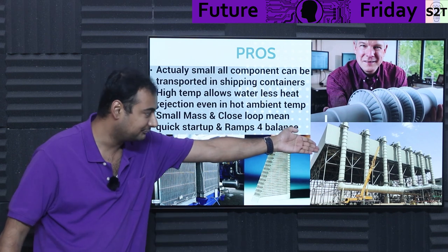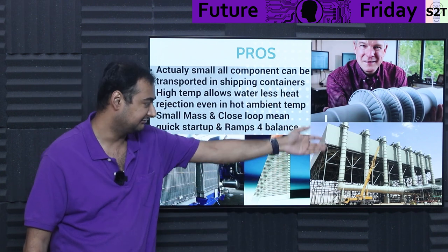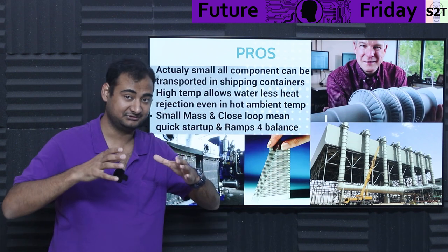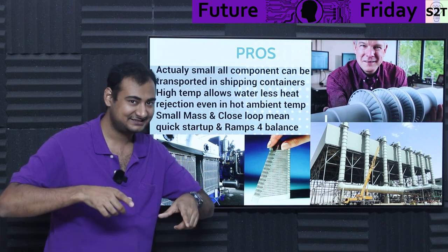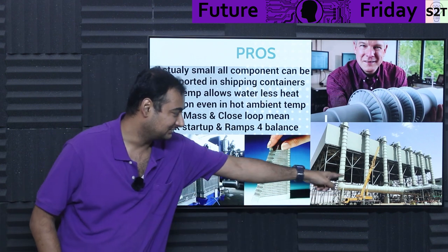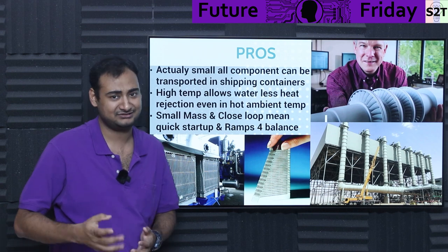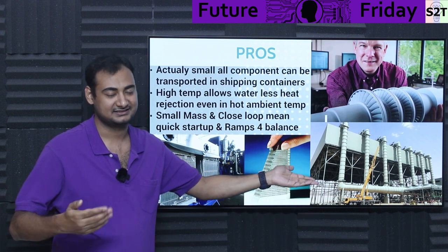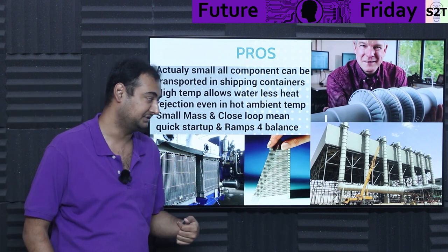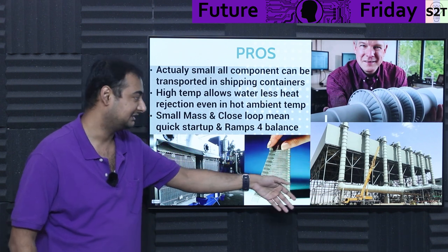Especially, again, if you can't afford this, you have to do this. And again, I do not even want to imagine how many trucks it would take to deliver that. The pipe section alone would be tedious. And my pipe would have to be very thick. Not only does it carry steam, it carries low pressure steam, meaning the atmosphere is trying to collapse the tube. With this sort of diameter, the atmosphere is trying to collapse you. It will be thick, even though you may think, oh, it will be thin. If you have minus pressure there, as in, let's say, rather than 15 PSI, you have 5 PSI, then 10 PSI of pressure is trying to crush you in. So you have to make it thick. So you understand that even though we can do that, that's why we don't do that.